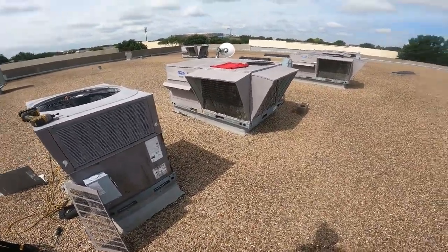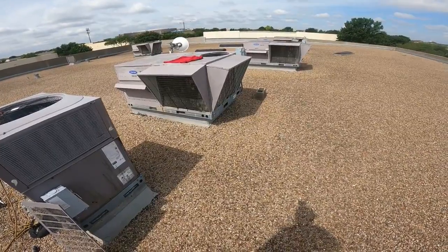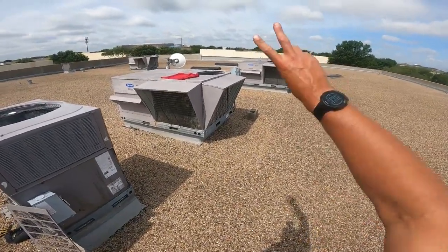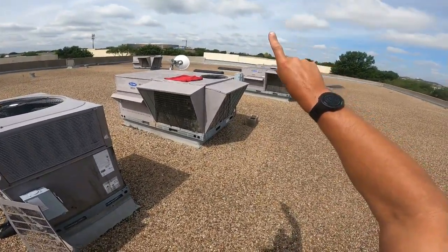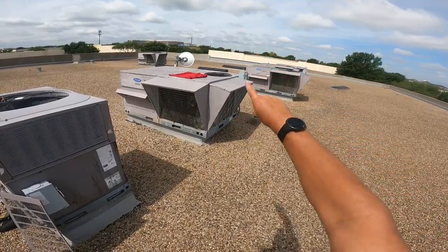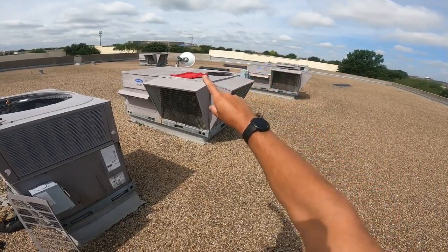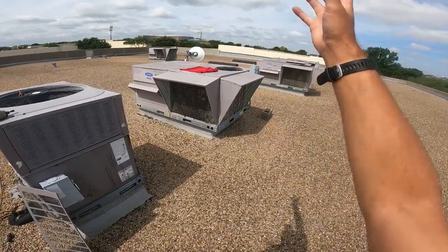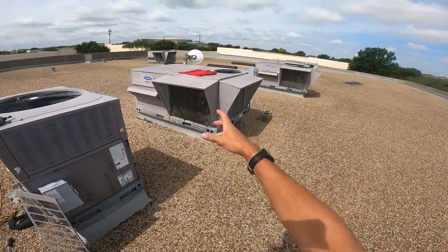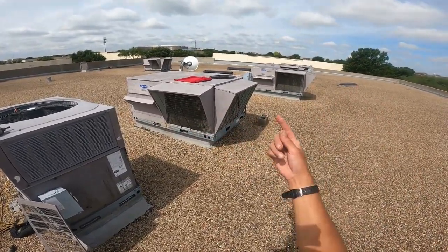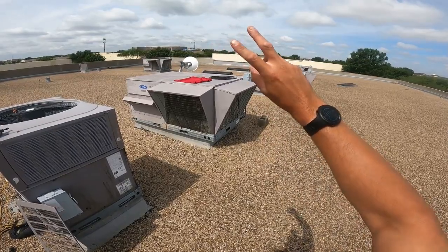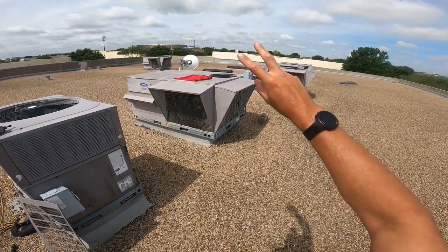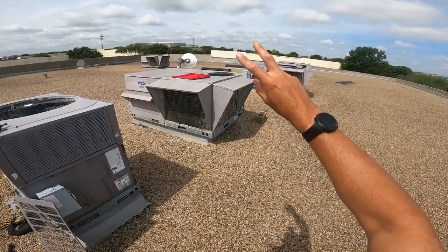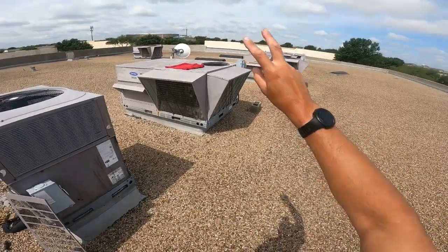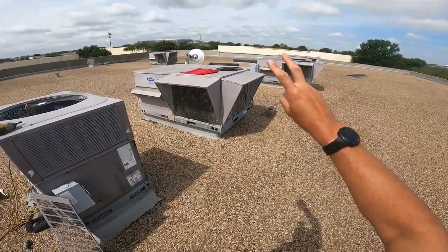Usually when fans go backwards, it's caused by one of two things. One, the fan that's working the right way is causing this one to go backwards, making air suck in through the hole, making the fan go backwards. Two, it's going backwards under power, which most of the time means that the capacitor's bad.